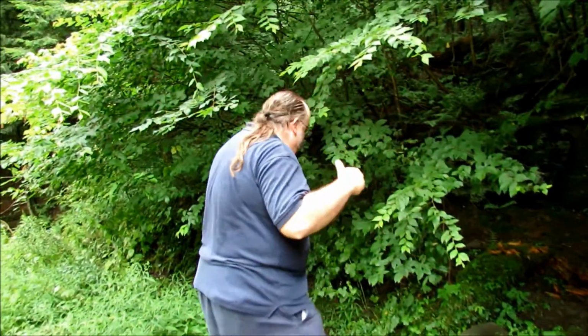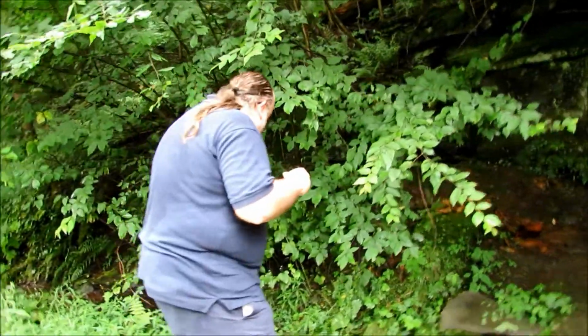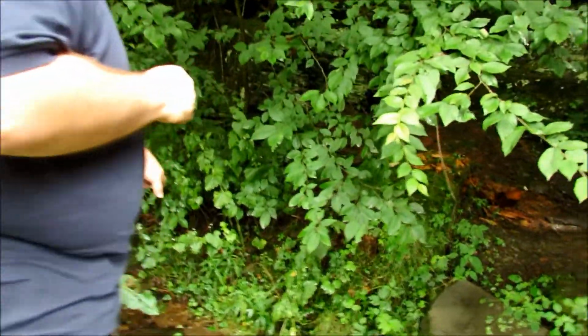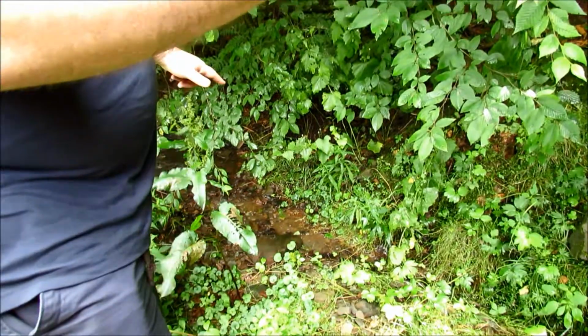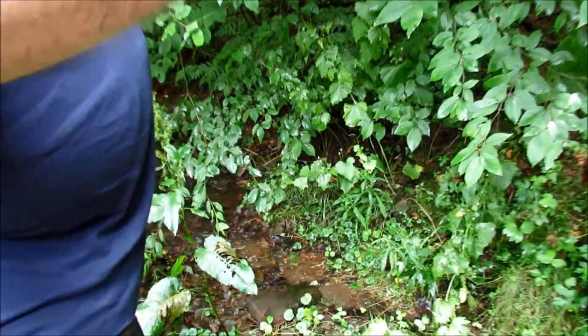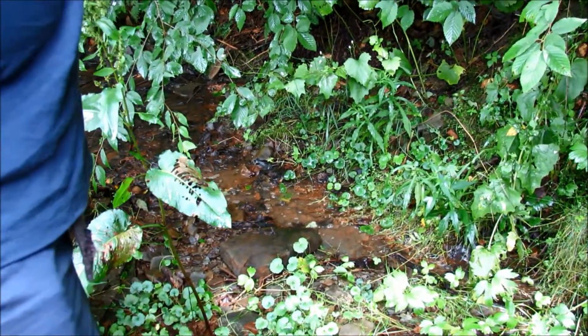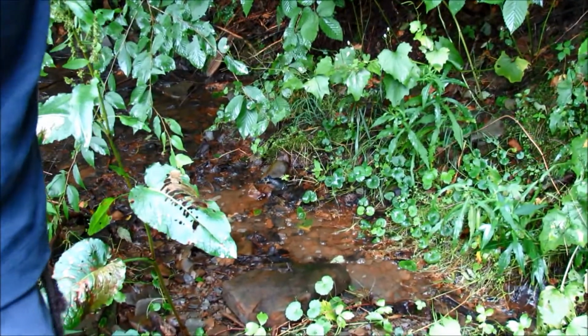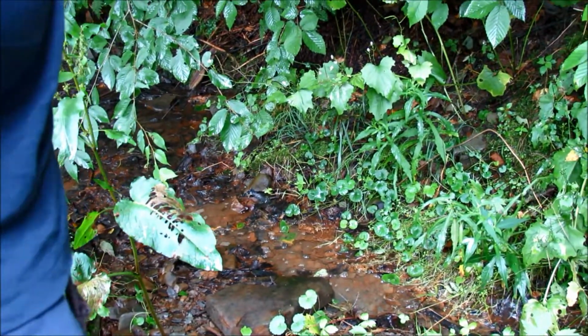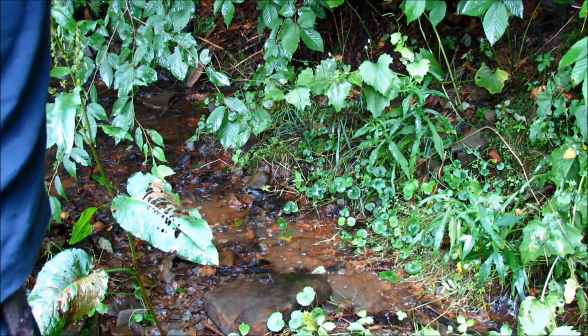If you come over here, you can actually see it's starting to oxidize. Oh yeah, see how it gets red? I see it. And so what's happening is the water's anaerobic. It comes out of the anaerobic as it hits the oxygen from the air. Ferrous oxide. Yep, we actually get a change, and we start getting that iron precipitate out.